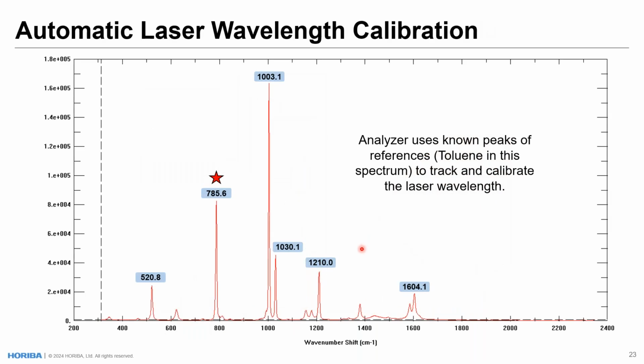So something that I mentioned earlier at the beginning of the introduction was our automatic calibrations. Our laser wavelengths, as we all know, lasers are not perfect. They do have the potential for wavelengths to drift a little bit over time, and the excitation laser drifting is not good for Raman spectroscopy because that will bounce the wave number shift around, for example. So when this happens, our analyzer will automatically recalibrate using known peaks of references.